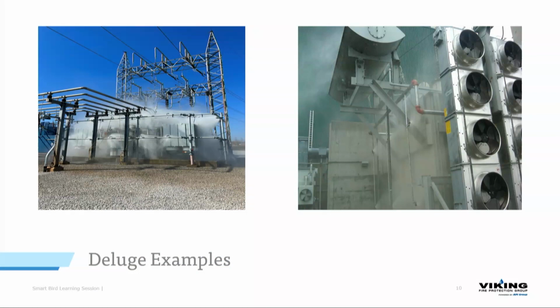Couple good examples here. This is very typical of what we see and what we do a lot of. We have a bank of transformers here. Again, we have like a 10 by 10 spacing, completely coating the exterior of these transformers. Very high rate of flow, as you can see. And again, over here, same thing. We've got a piece of equipment that is completely being doused by water.